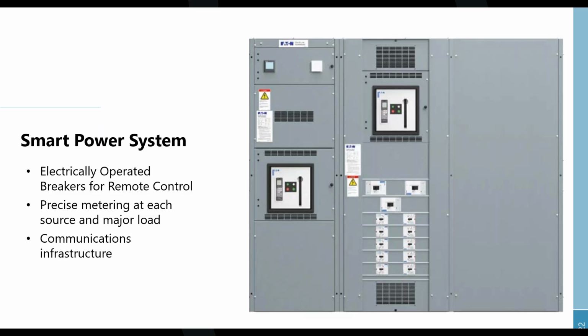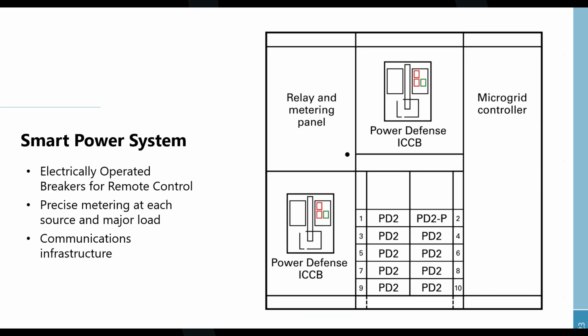The power metering and control features required to run a microgrid are simply commonly available industrial grade components that have been around for decades. On the next slide we can see that same switchboard described. This particular manufacturer has the microgrid controller integrated into the switchboard on the right side, but that's not required. Most of the time it's going to be on a control panel on the wall in the electrical room, with communication conduits connecting over to this smart switchboard, which can operate all the breakers and take in all the metering remotely.